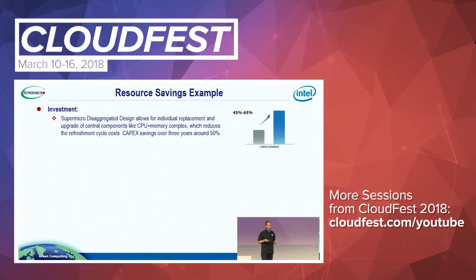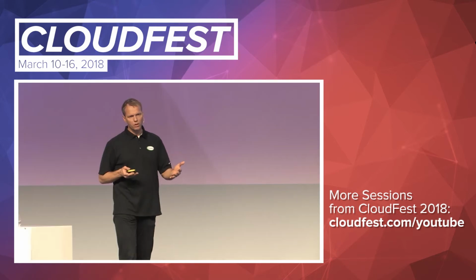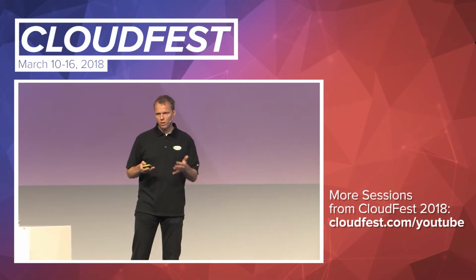Investment cost: as I pointed out, due to the disaggregated design, it is possible to upgrade your solution to the next level - for example, in this case, it was the new socket and new memory subsystem - by keeping the storage, the cooling, the power supplies, and the entire chassis. So the calculation we did with our customer here resulted in an estimation of savings of more than 50%, up to 65%, depending on certain parameters.